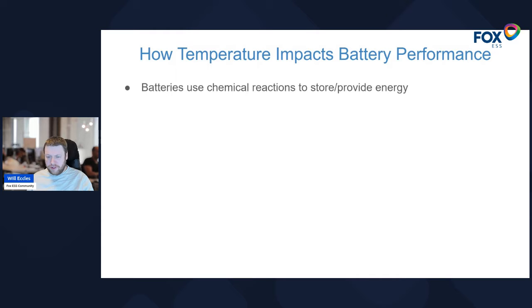The downside of lithium iron phosphate is they are quite temperature sensitive. When batteries start to cool below around 15 to 12 Celsius, performance and capabilities start to slowly fade away, only temporarily while at that temperature. They're quite good on the higher end, stable until you start to go over 30 to 40 Celsius, with a maximum around 50 Celsius for most LFP batteries. When Fox or anyone is selecting the chemistry for a battery product, they've got to figure out its typical use, its typical environmental requirements when it comes to temperature, what life they want out of it, how many cycles, what charging and discharge currents they want to support, as well as the temperature band they want it to operate within.